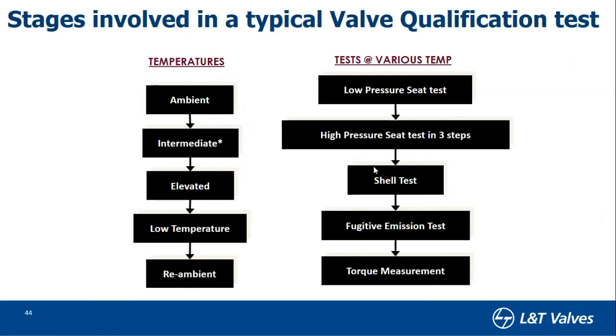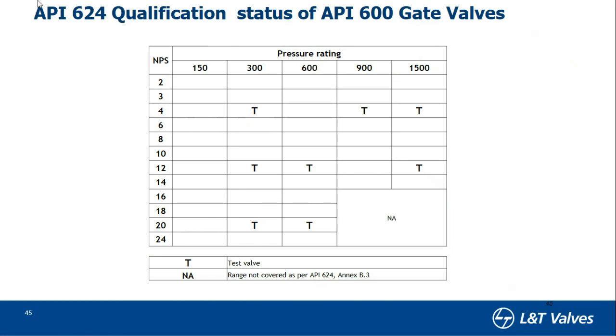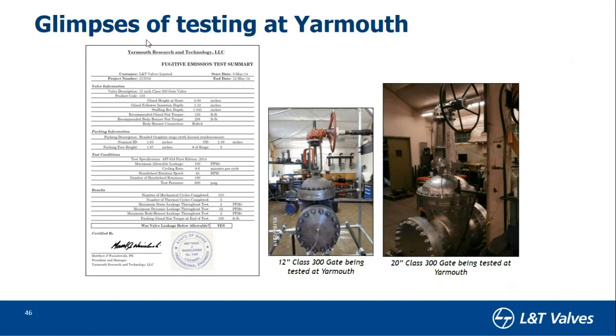The stages involved in qualifying a valve to fugitive emission standards are: low-pressure test, high-pressure test, shell test, fugitive emission test, and torque measurement. For API 624, the valve range is API 600 gate valves from 1 to 24 inch in Class 150, 300, and 600. The standard identifies specific test sizes (e.g., 4-inch Class 300, 12-inch Class 300, 20-inch) — qualifying these sizes qualifies the entire range. Testing is typically done at an independent laboratory, such as Yarmouth in the US. This qualification test is both expensive and time-consuming.